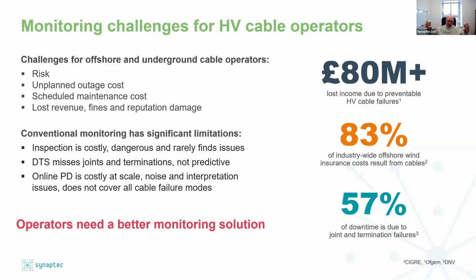It's the joints and terminations where most of the failures are happening. And I've seen published data saying that's about 57% of all failures that have been analyzed in recent DNV reports. But whenever I speak to customers and operators, they always tell me, no, it's much higher. We've heard 70 or 80% in different cases. So the majority of the failure is happening where a human was involved, either terminating or connecting that cable. It's the link boxes, the joints and the terminations where you have the problems. It's not the cable itself.